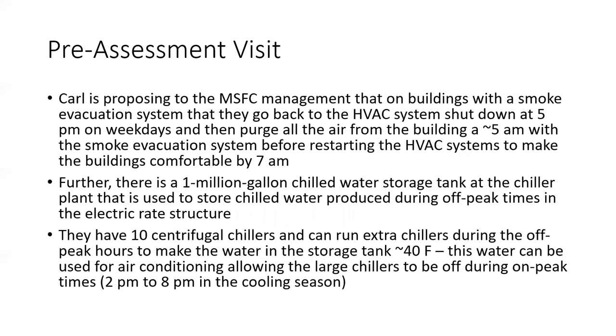So he's proposing that they go back to the shutdown on the weekdays from 5 p.m. and then at someplace around 5 a.m., instead of just the first thing being starting up the HVAC system, the first thing would be to turn on the smoke evac fans and completely purge all of the air out of the building. The idea there is he can guarantee to the safety people that if there was anybody in there that had COVID, and it's possible, well, they probably weren't working overnight if the HVAC was off, but they could have been in there the day before, and there could still be COVID in there.